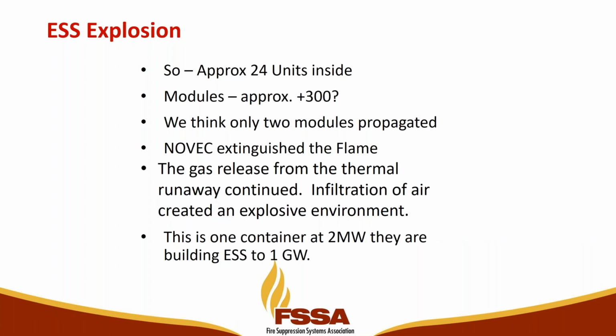So there are approximately 24 units, and units can be interchanged with the term rack, cabinet, whatever you want to call it. Probably modules, each containing somewhere around 22 to 24 batteries. So there were probably 300 plus modules. We think that only 2 modules propagated, or 1 rack. NOVEC did extinguish the flame, but the gas continued to release. And thermal runaway continued, propagation continued.